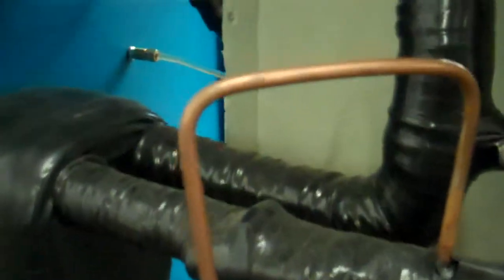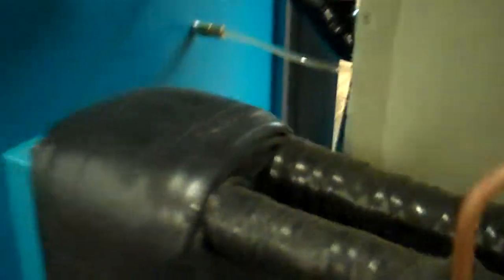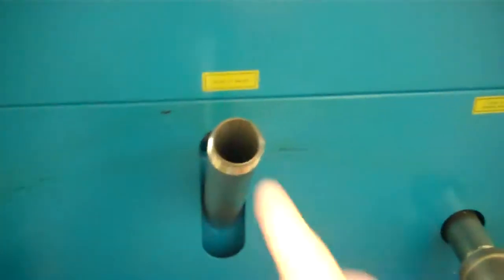We have an 8 horsepower Copeland scroll compressor. We have our dryer in the line here, our thermo expansion valve. These units use a nice brazed plate heat exchanger. We have our incoming water, our outgoing water. These are 1-inch connections on the 8-ton. This is just a filler inlet, and you have your drain in the back of the unit.